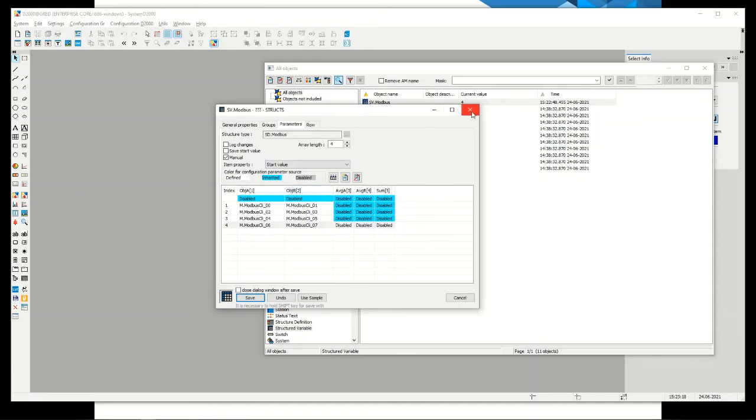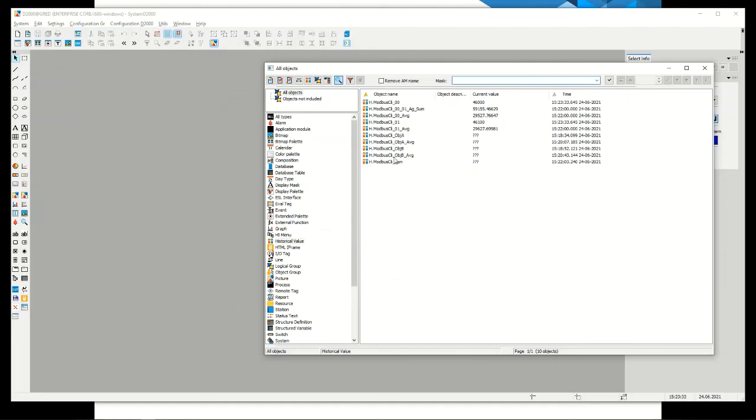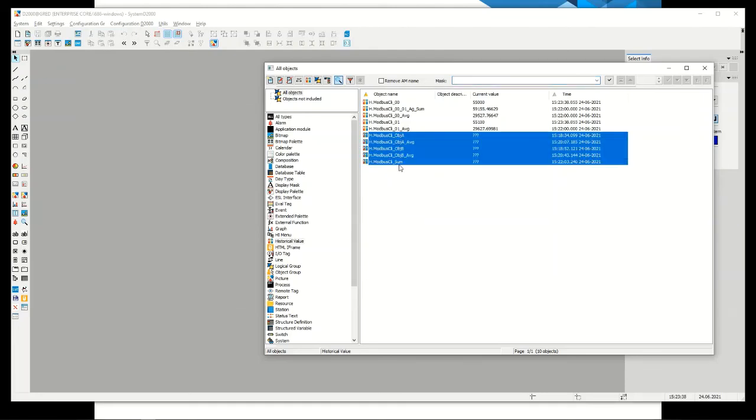So I can have 20 rows or 50 rows. All I need is to connect another object, I/O tag or something else, to the structure and resize it, and I don't have to touch my historical values. Again, I want to also tell you that these 5 structured historical values are all that is needed for even tens or hundreds of I/O tags if they are connected to my structure.